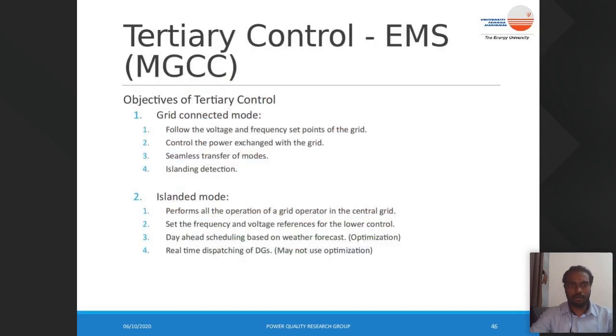We have come to the top of the control hierarchy. We call it tertiary control or energy management system, or even the microgrid central controller. Based on the configuration of the secondary controller, the secondary controller can be clubbed with the tertiary controller to form a microgrid controller. If it's a decentralized one, tertiary control still remains in the microgrid central controller.